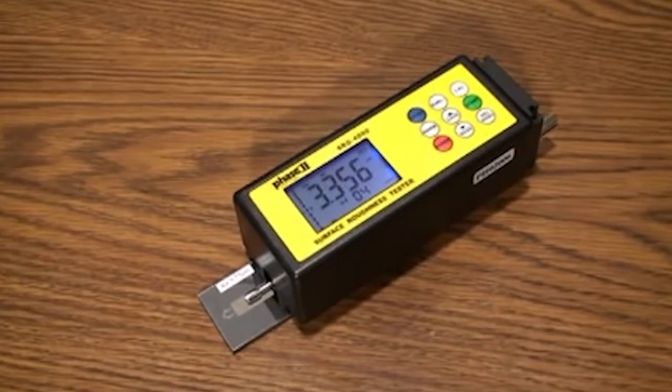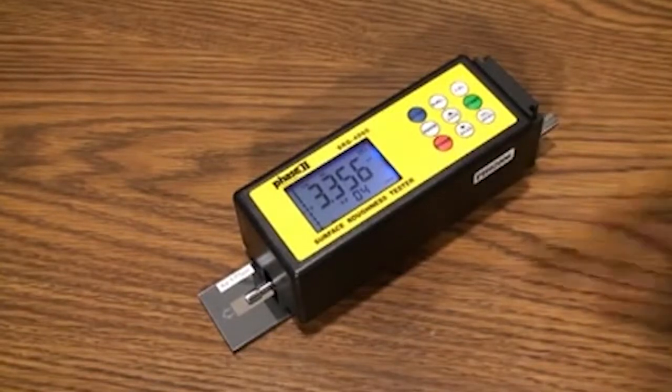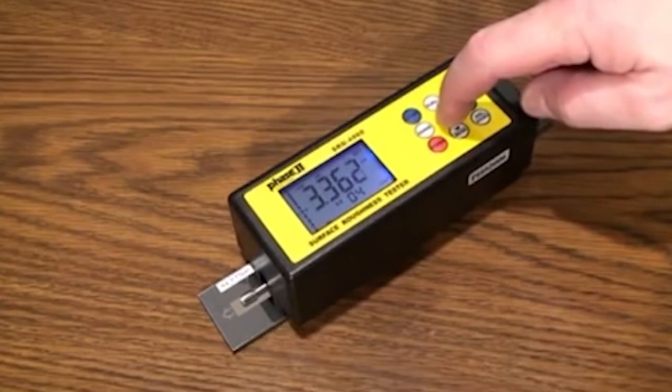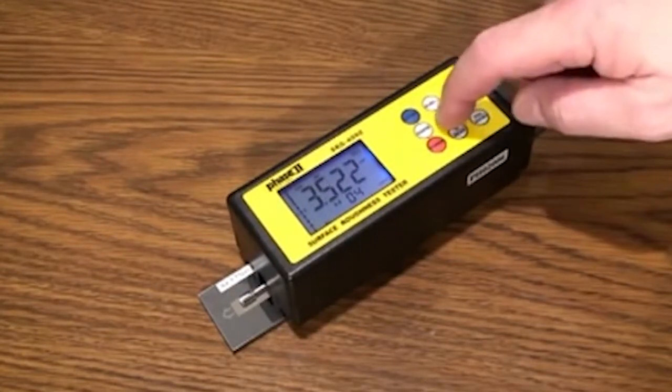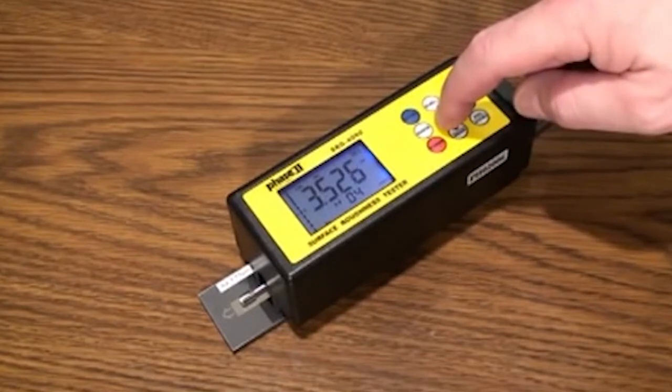Press Start to take a test. If the value shown after test is different than values shown on the sample, use the up or down arrows to adjust the reading. Hold down arrow buttons while tuning until value begins to change. Once you have correlated the value...